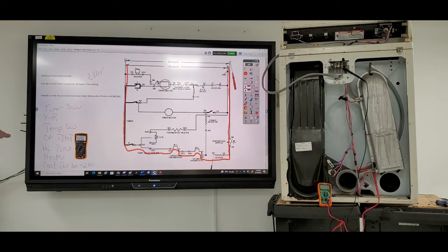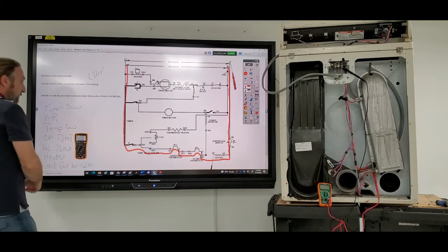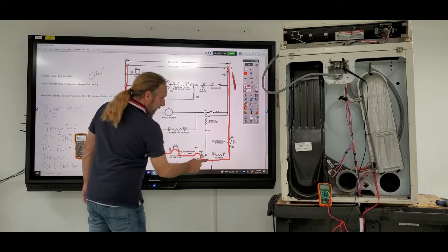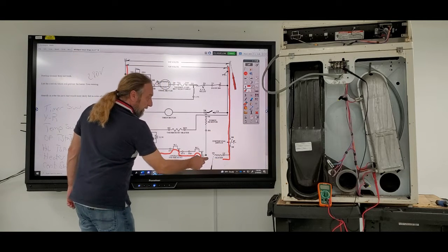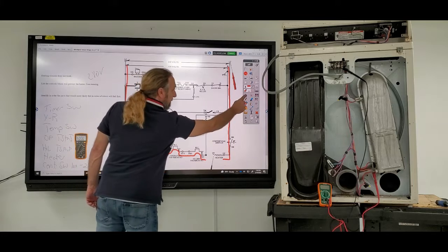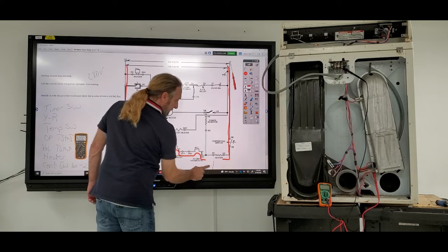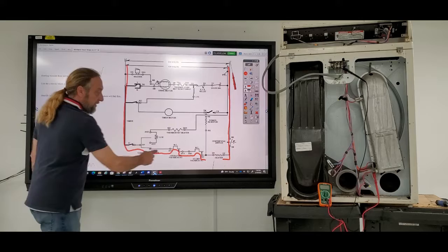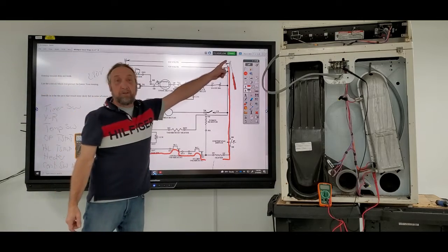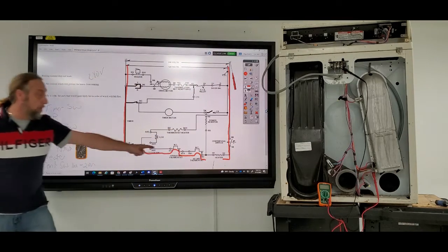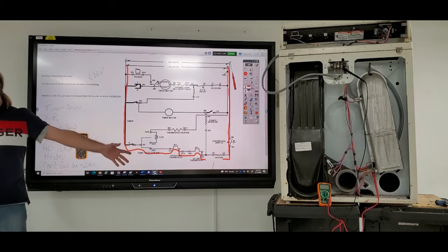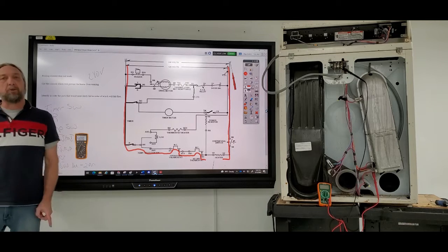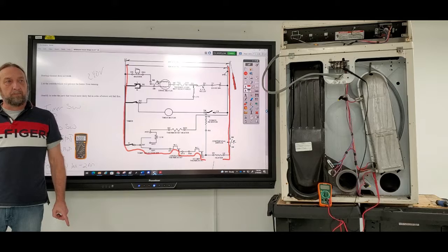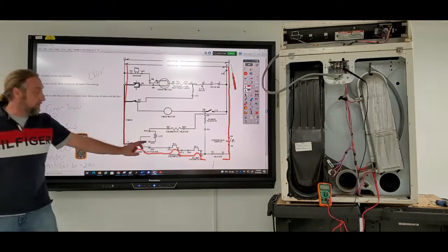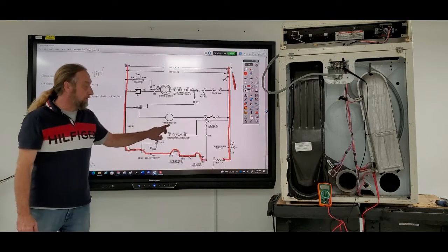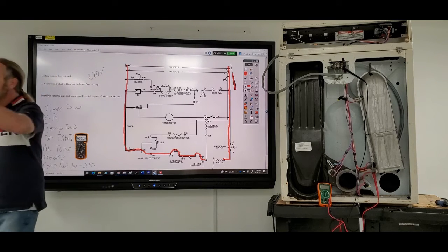I don't need to check any of those, because in order for me to get 240 volts, my meter lead has to go up to this point here. My voltage is up to here, and my voltage is there. I know that all of these are good because I have voltage where that meter is. I just tested 1, 2, 3, 4 components by moving one meter lead.